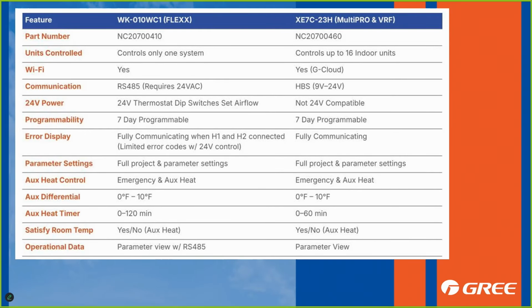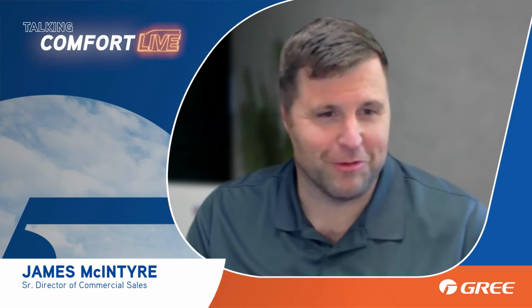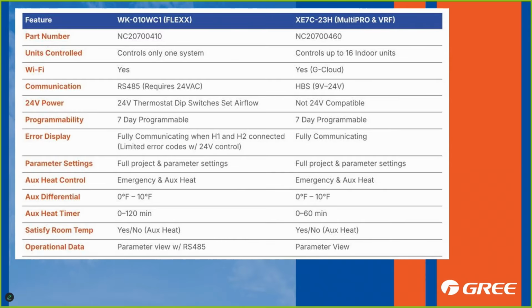They're both 7-day programmable. Error code display. With a fully communicating system, you're going to have error codes that will appear on the wired controller. So on the FLEXX, if you've got your H1, H2 connected and you're using this wired controller, with a fully communicating system, you'll see the error codes displayed on the controller. You don't have to wait for it to get hot in the house before the customer calls and says, "Hey, I need somebody out here immediately." They can have an error code, maybe they reset power and they can run for a little while until you get there. That's one of the benefits of using an inverter-driven system. But both will show those error codes.